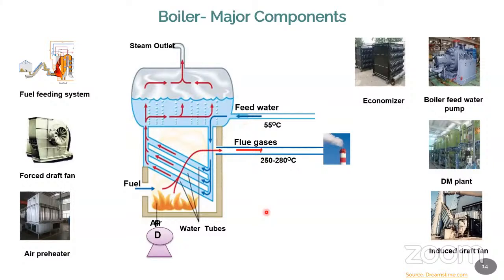So when the temperature is not reached, what will be done? The boiler operator will feed more wood inside the chamber. So ultimately, the fuel consumption will increase. Now it is recommended to pulverize the wood, or at least cut the wood. It has two advantages. Number one, if you cut the wood and keep it in the atmosphere for some time, the moisture inside the wood will be taken out. When the moisture is taken out, automatically it will burn easily, and it will release the energy very quickly.